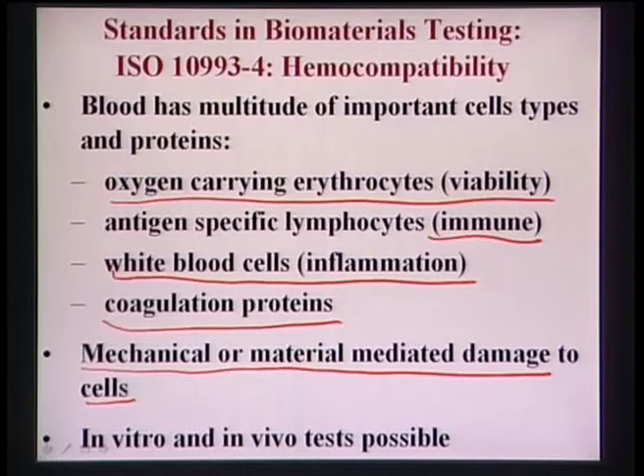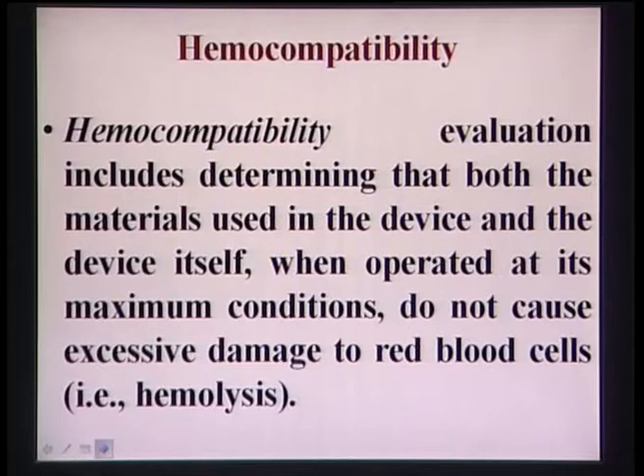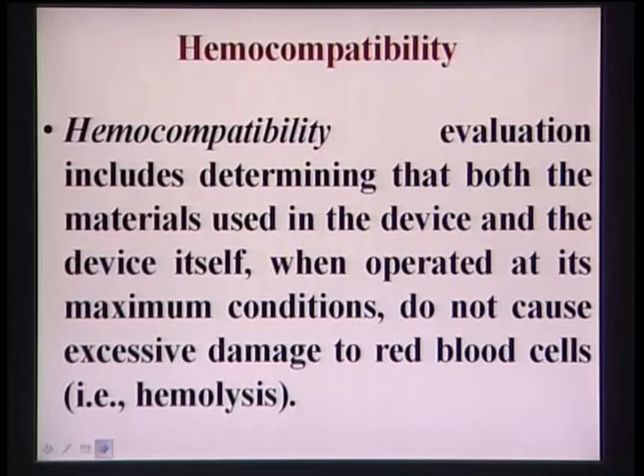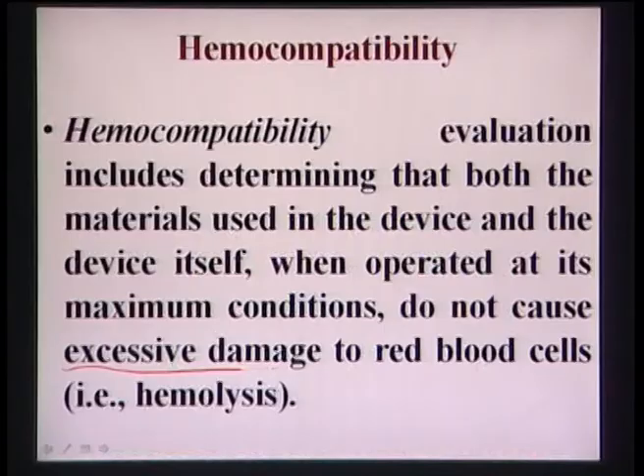Blood compatibility testing can be done both in vitro - laboratory simulated tests - and in vivo - experiments conducted inside animals. This biocompatibility test includes determining that both the materials used in a device and the device itself, when operated at maximum conditions, should not cause any excessive damage to RBCs or hemolysis. The word 'excessive' is important to underline.